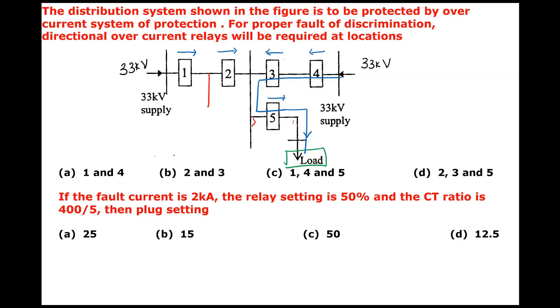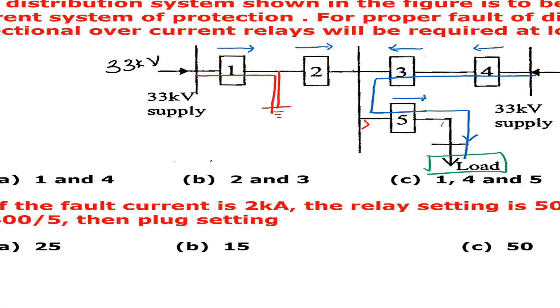If a fault occurs here, we are only worried about the fault current directions of relay 1 and 2. The fault current through relay 1 will flow in this fashion, and the fault current through relay 2 will flow in this direction. These are the fault current directions written in red. Now you have both the normal current direction and the fault current direction.